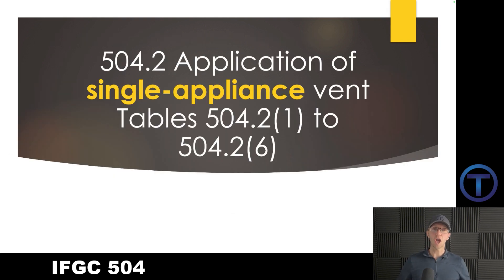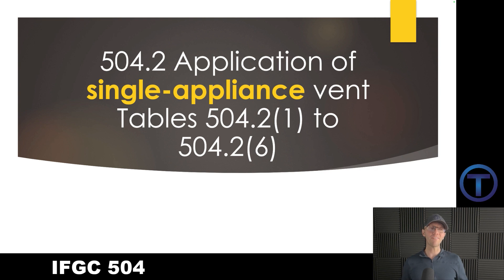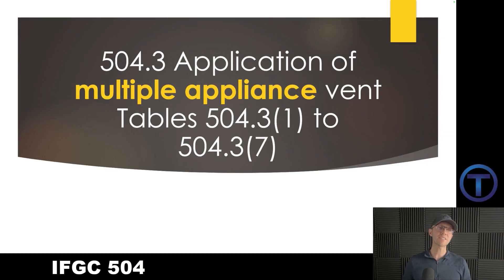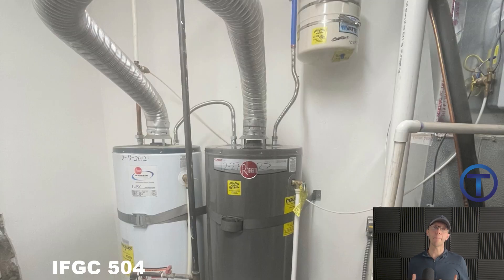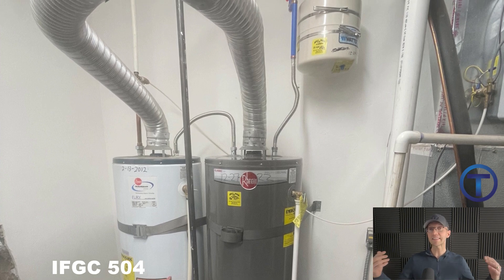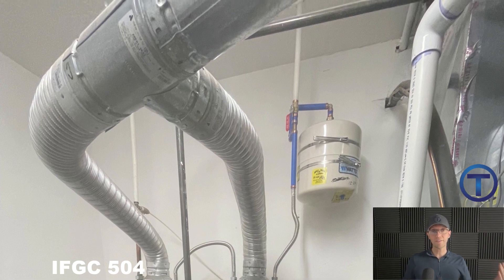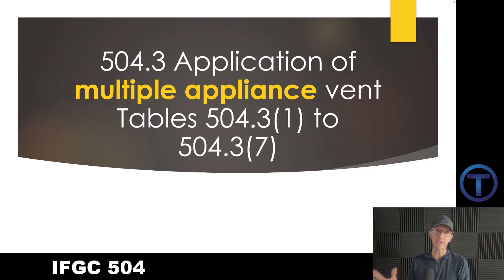There are several sections loaded with tables. Take a minute, flip through your book and notice how many pages are packed with sizing tables. One of those sections is 504.2, which is the application of single appliance vent tables — meaning you have one appliance and one vent for that appliance that goes to the outside. There is another set of tables in 504.3, which is the application of multiple appliance vent tables. This is where we have several appliances, maybe several water heaters coming together on a vent, or a draft vent furnace with a water heater coming together in a common vent.